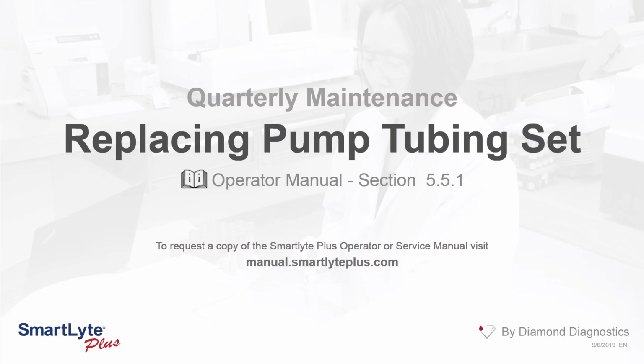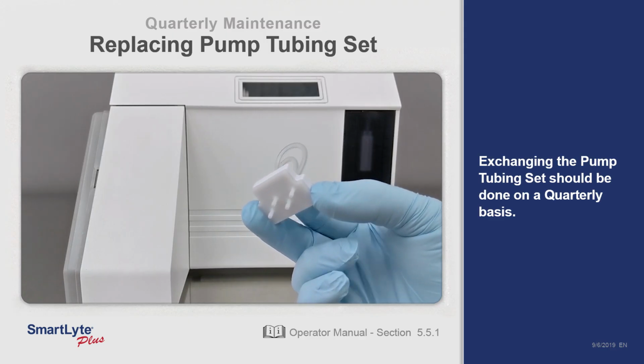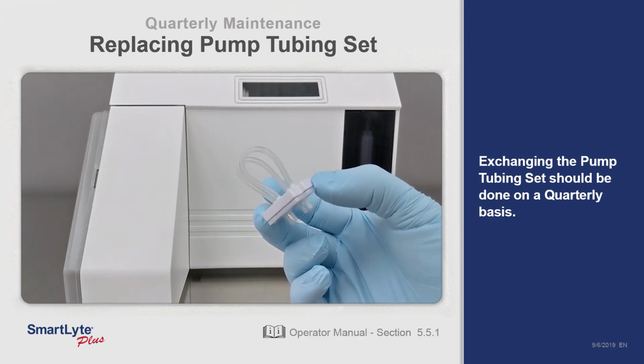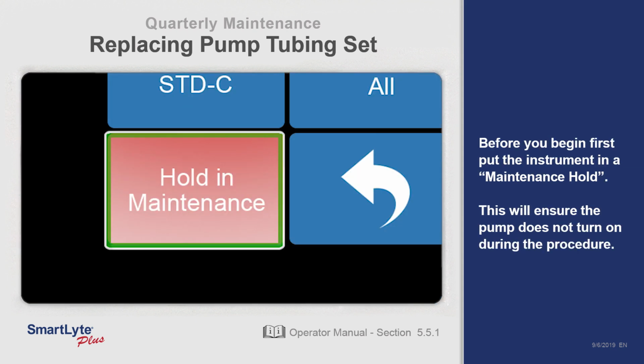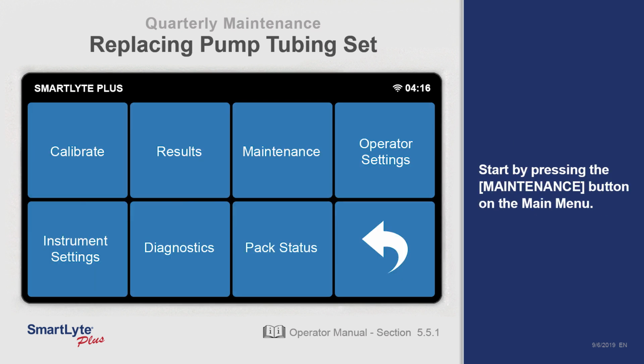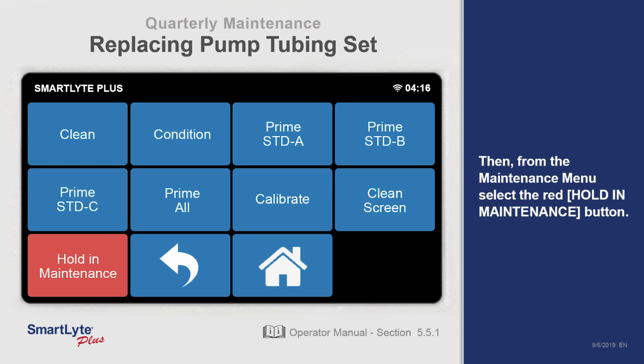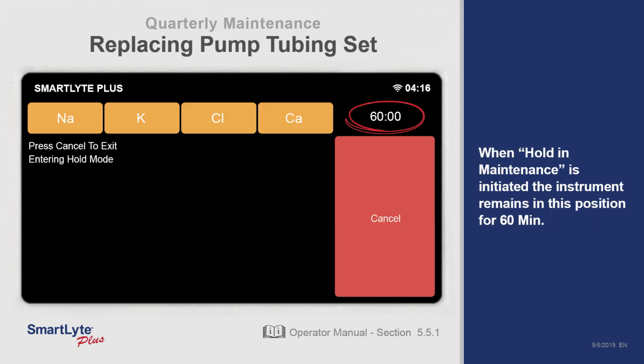Replacing the pump tubing set. Replacing the pump tubing set should be done on a quarterly basis. Before you begin, first put the instrument in maintenance hold. This will ensure the pump does not turn on during the procedure. Start by pressing the maintenance button on the main menu. Then, from the maintenance menu, select the red Hold in Maintenance button. When Hold in Maintenance is initiated, the instrument remains in this position for 60 minutes.